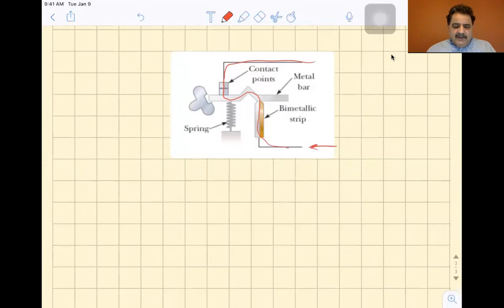Well, if this gets too warm, this is a bimetallic strip and whether you covered it or not, the different metals expand at a different rate for temperature. So they have it here where this brass colored or copper colored piece of metal will expand faster. And if there's too much current, it'll expand faster. It'll get warm, expand, and it'll curve to this side.